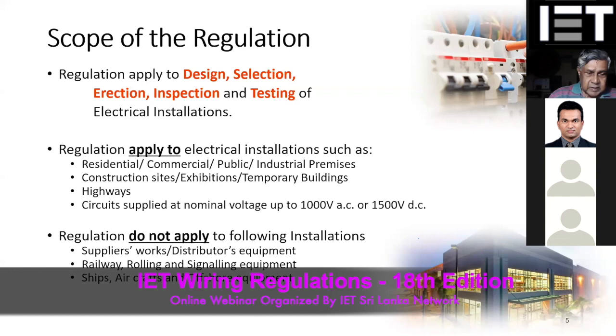So there is a limit. The voltage should be less than 1000 volts AC and 1500 volts DC, and it should be a residential, commercial, or public type of installation or construction site. Then we can apply this regulation to that type of location. But the regulation clearly mentions that even though the voltage is less than 1000 volts AC or 1500 volts DC, it is not applicable to the supplier's work. For example, the utility, CEB or LECO distribution system: you cannot say our regulation is this and you have to follow it, because distribution codes are there separately, even in Sri Lanka, which the utility should follow.